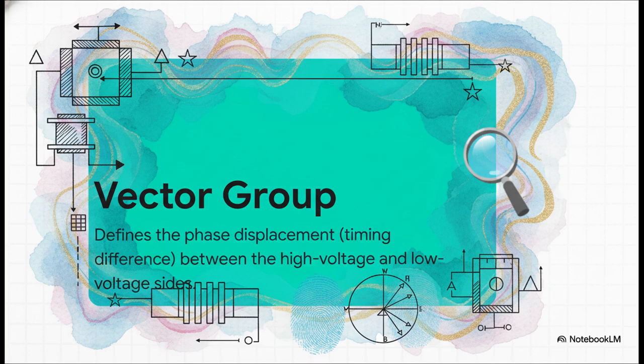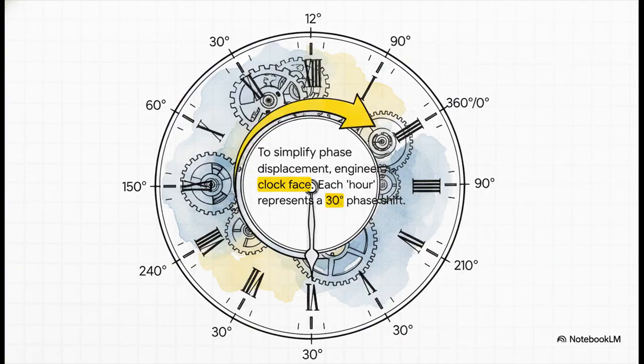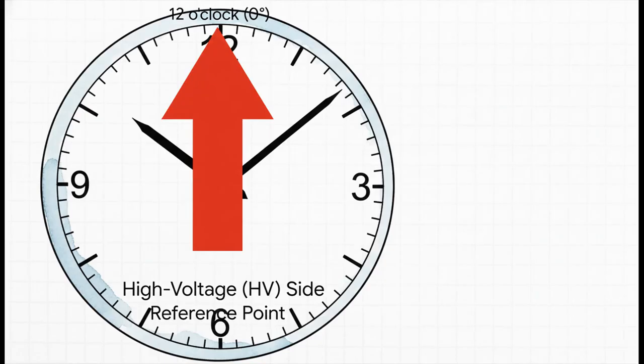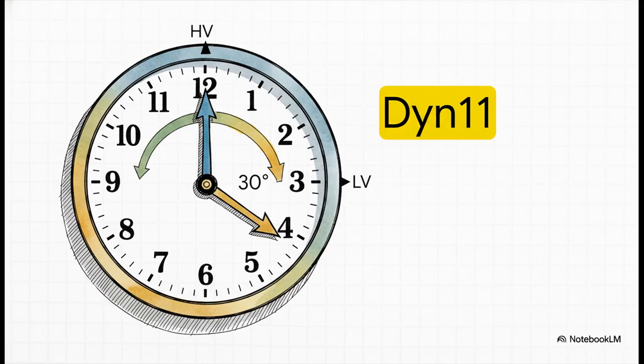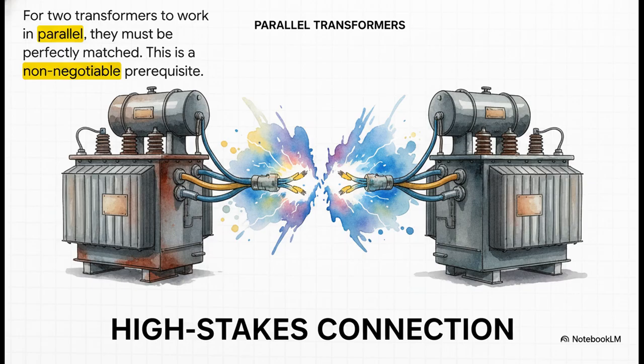This brings us to the vector group. Think of it like a transformer's unique fingerprint. It's all about timing. To make sense of this, engineers use a clever analogy: a simple, familiar clock face. The high voltage side is always set to 12 o'clock. That's our reference point. So if you see Dy 11, it just means the low voltage side is at the 11 o'clock position. Simple. And this timing is absolutely critical when they have to work together.